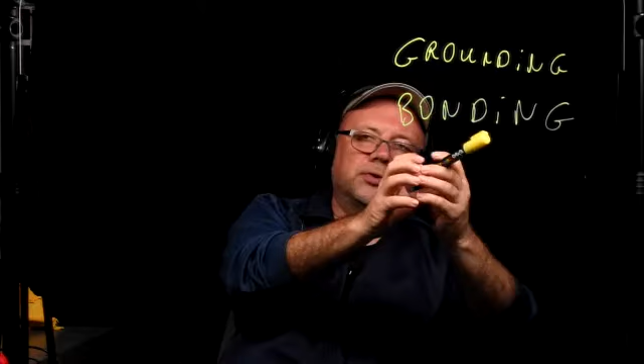So it has one uninterrupted pathway from that terminal to a true ground, usually a spike, plate, or true ground provided by the construction. Now when we have that terminal connected to another terminal with a straight wire, that secondary terminal is also electrically connected to the true ground, but it doesn't have a direct pathway - it goes through another terminal first, joined there, then to the true ground. So that terminal is considered bonded. What do you mean by bonded? It is connected to ground, it is bonded to ground. Generally we'll just say that terminal is bonded, and the first terminal that goes through a true ground is grounded. That's the jargon you're going to hear.